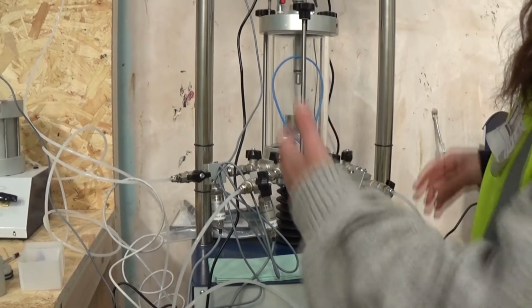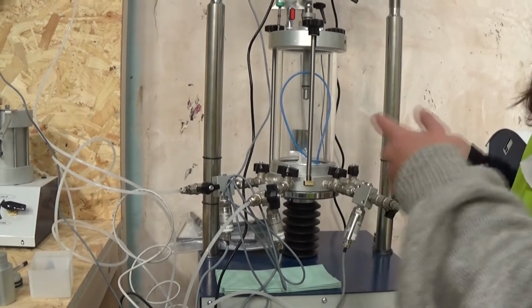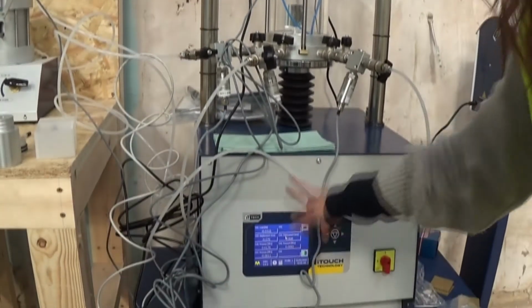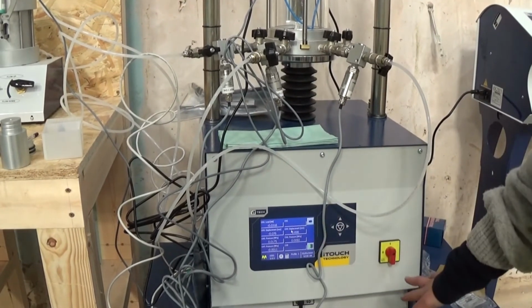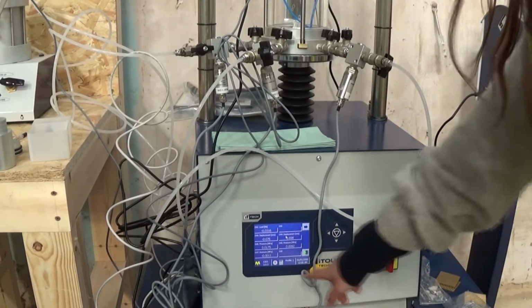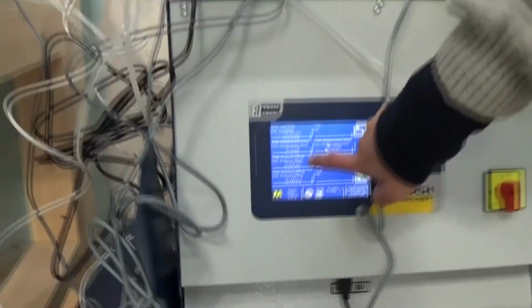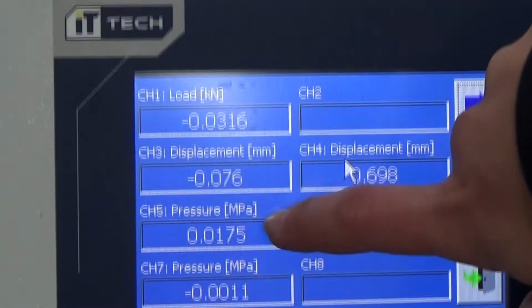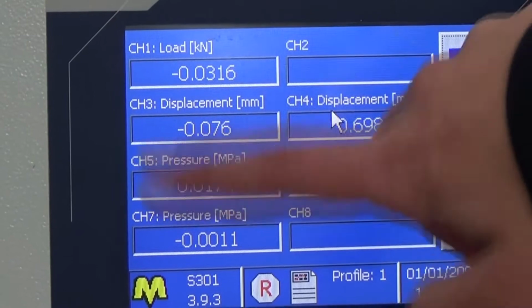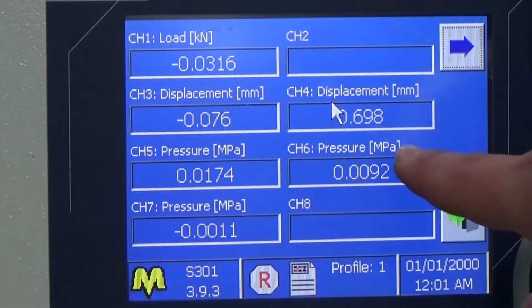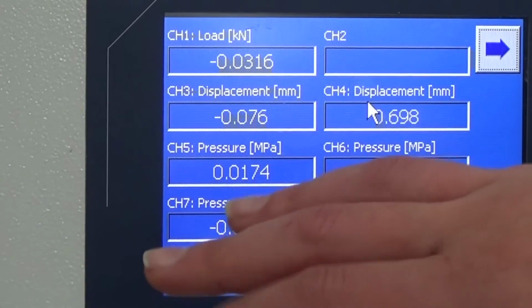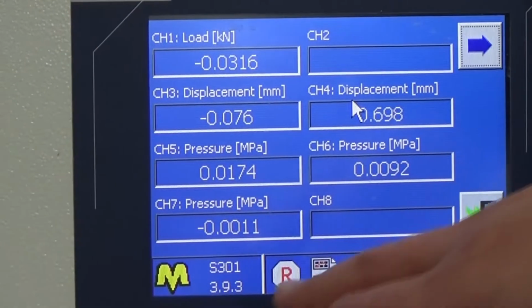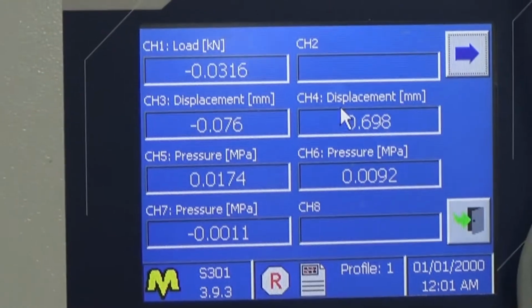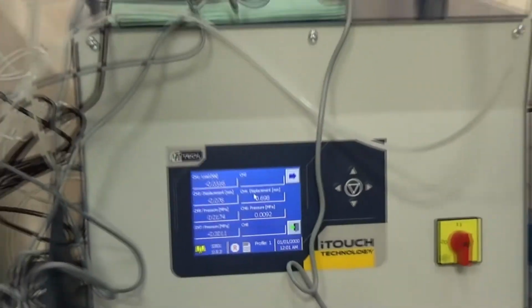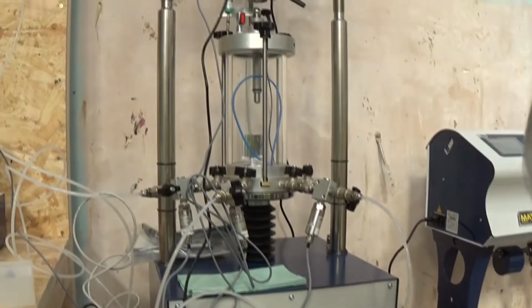For this reason, you will see the same value on the panel and the machine according to the right pressure transducer. It's important to see that the panel is in kPa and the machine is in megapascal. So you need to be careful about the value that you read, because the unit is not the same. But the value is for sure the same.